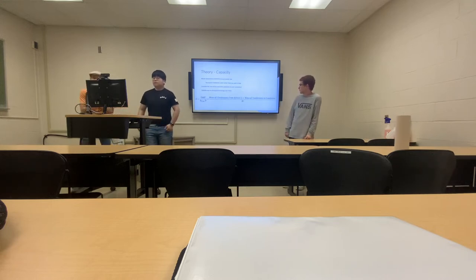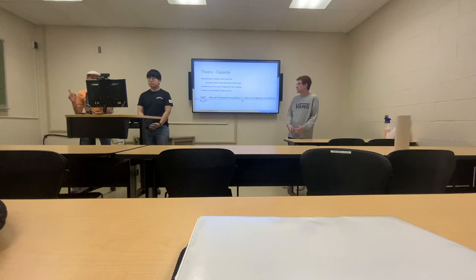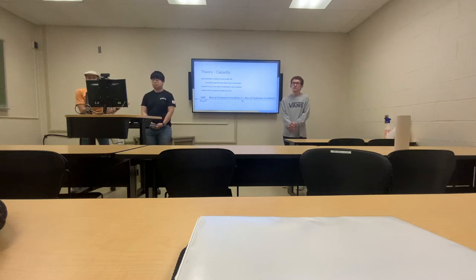Capacity is based off of the rate of evaporation, or the amount of condensate that you can form. Basically, you can't evaporate water faster than you can add energy to the water. So you're limited by the heat transfer rate. Functionally, that looks like the rate of mass production of condensate, which means that you can actually measure what's coming out of the bottom of your evaporators if you want to figure that out.